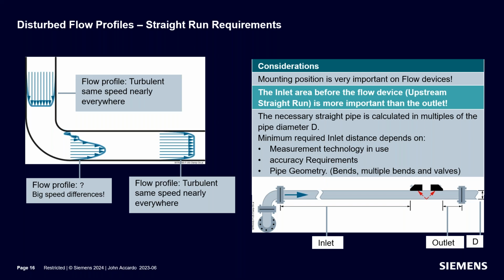Well, back in the early 90s, well, actually before that, we were seeing applications where we were getting enhanced errors for no seeming reason at all. There was 20 diameters of straight pipe and we should be in perfect shape, and yet the flow meter was reading incorrectly. And so Controlotron was one of the primary sponsors of a research project done at the NIST in the early 90s that measured the effects of differing pipe geometries on flow profile. And the results of those tests were that it was determined that the traditional 10 and 5 rule isn't always ideal. It all comes down to what is upstream. How many elbows are there, and how are they relative to one another?